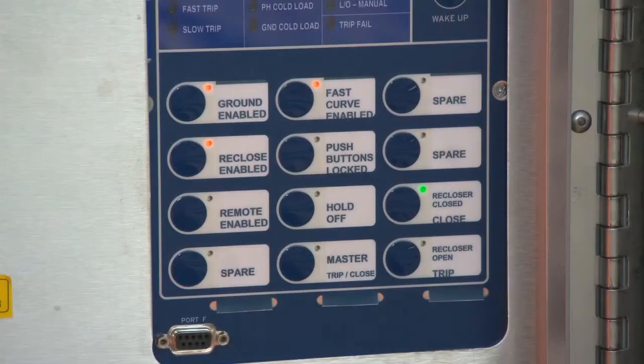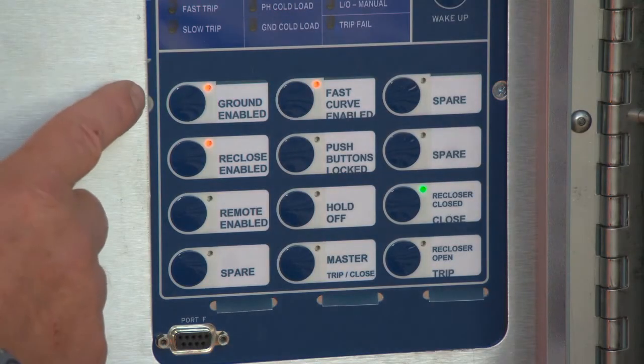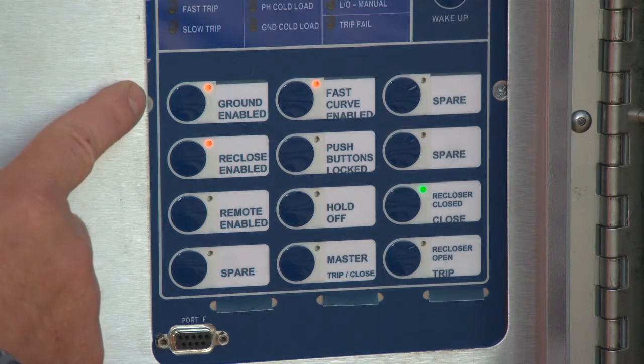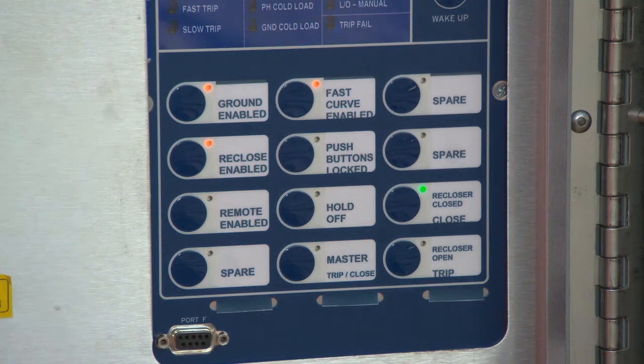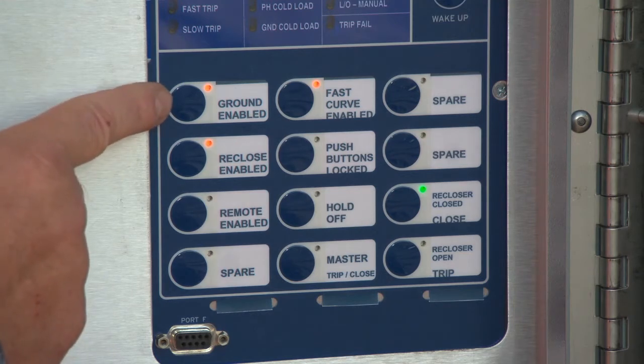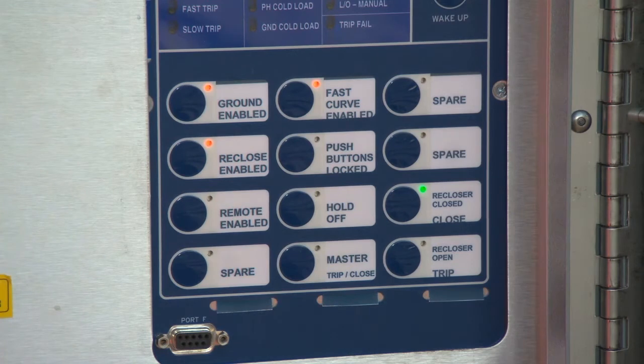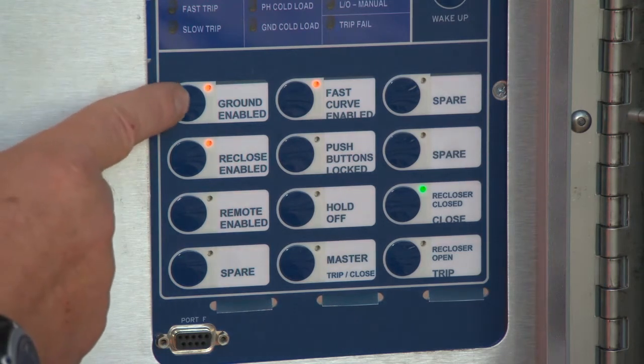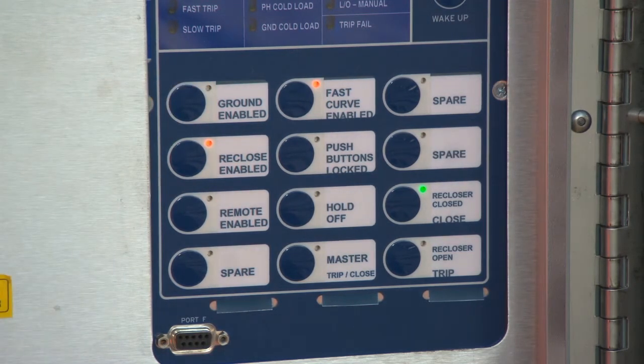There are 12 push buttons on the bottom of the control that function as pre-programmed action buttons. Ground enable. In order to turn off the ground to avoid the recloser from tripping on a ground function, press the ground enabled button once. Push again to turn the ground back on. This is typically used in switching operations.